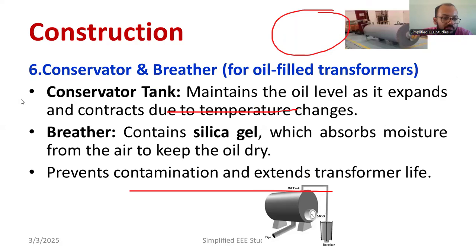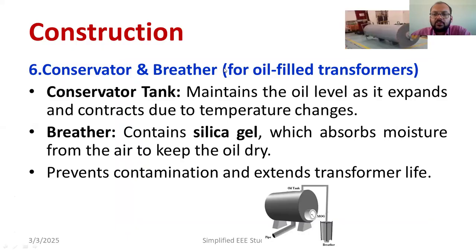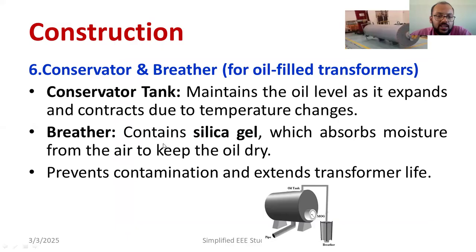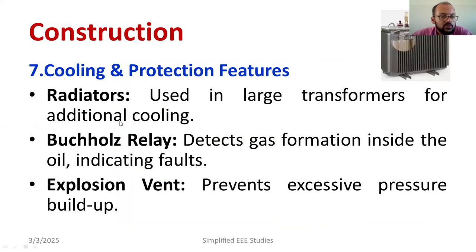Now I will discuss the conservator, where transformer oil is stored. There will be a special indicator, and the expansion depends on the temperature rise. Along with the conservator, there will be a breather — silica gel is used as a breather, which absorbs moisture and keeps the oil dry. This is important because if there is moisture content, the quality of the oil will be spoiled.